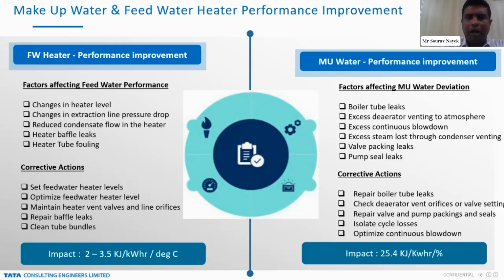Now, after selection of the feed water heater and the configuration and design parameters, in the ongoing plant there will be multiple factors which will affect the feed water heater performance, like changes in heater level, the extraction line pressure drop to heaters, the reduced condensate flow, then baffle leaks, and heater tube fouling. These are the key aspects which impact the feed water heater performance.